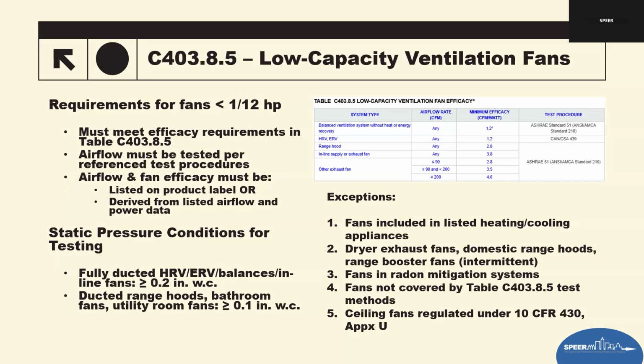Testing and documentation requirements. The airflow must be tested using an approved test procedure referenced in the table 403.8.5. The results must be listed on the product and or derived from a manufacturer listed airflow and input wattage. So you can look at that part of it and see, and this ensures the inspectors and designers can verify performance without guesswork.